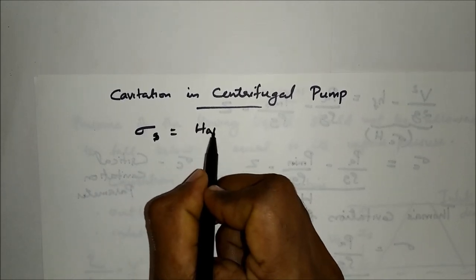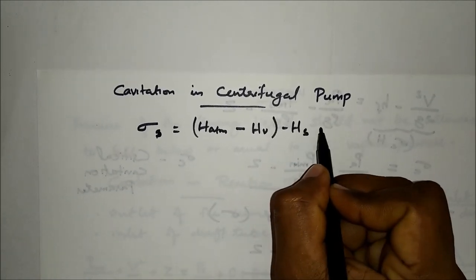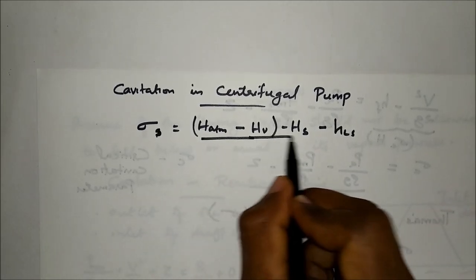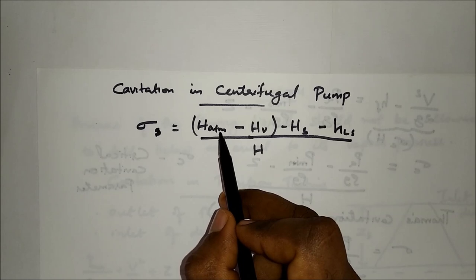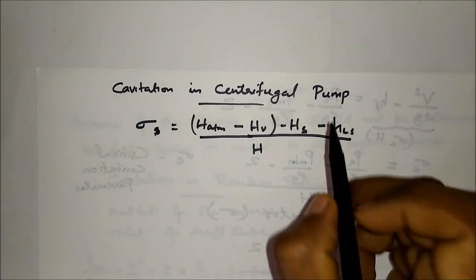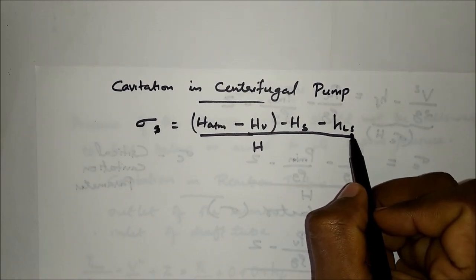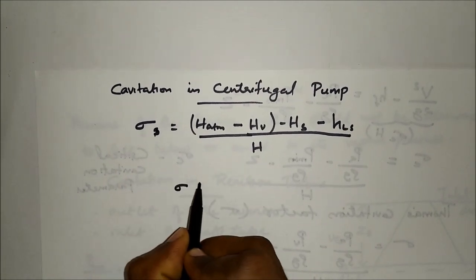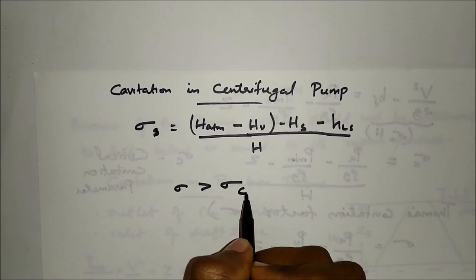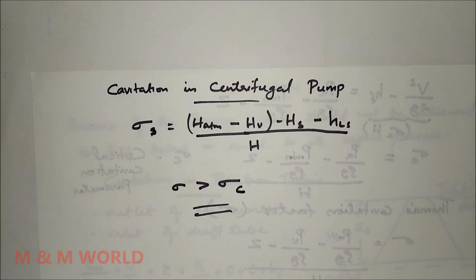The Thomas cavitation factor for centrifugal pump: σ = (H_atm − H_v − H_s − H_ls) / H, where H_atm is the atmospheric pressure head, H_v is the vapor pressure head, H_s is the suction pressure head, H_ls is the head loss due to friction in the suction pipe, and H is the head developed by the pump. In order to avoid cavitation, σ must be greater than σ_c, that is, the Thomas cavitation factor must be greater than the critical cavitation parameter.